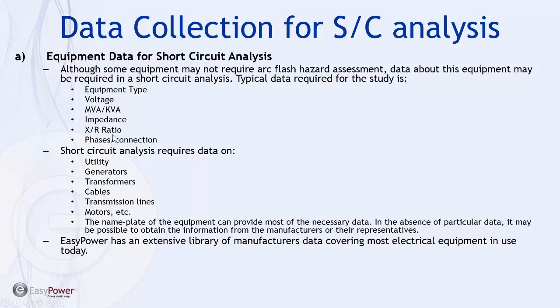Most of this on larger equipment will be on a nameplate. Short-circuit analysis requires data from utility connections, generators, transformers, cables, transmission lines, and motors. The nameplate of the equipment can usually provide most of the necessary data. If you're missing something specific, you can usually get that from a manufacturer's data sheet. In some cases, the tools can help connect the dots based on what you have, given the extensive library in the EasyPower tool suite.